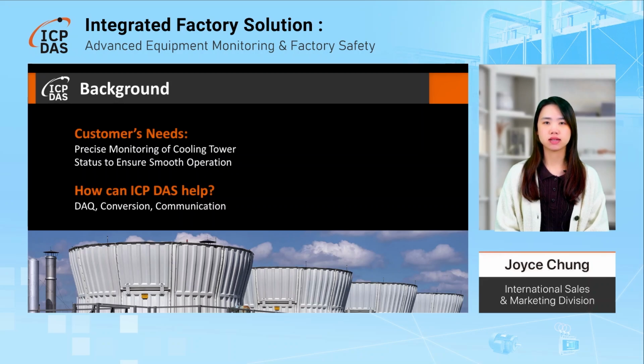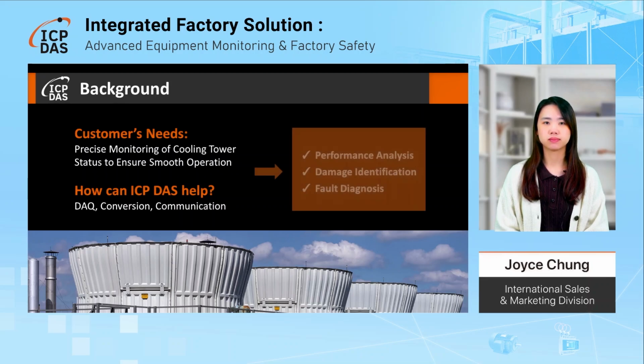So how can ICP-DAS help in this case? With holistic product lines, we offer a total solution that combines DAQ, conversion, and communication. By utilizing this solution, ICP-DAS help achieve data collection, real-time performance analysis of the cooling tower, fault diagnosis of the fan drive system, and damage identification in the cooling system.